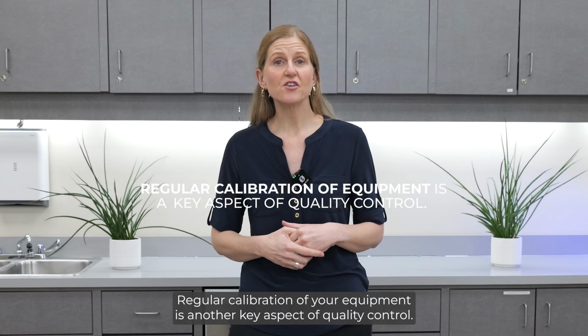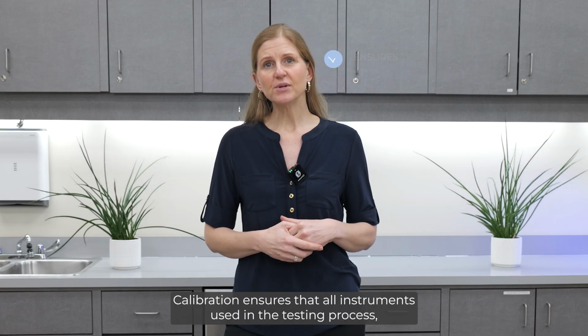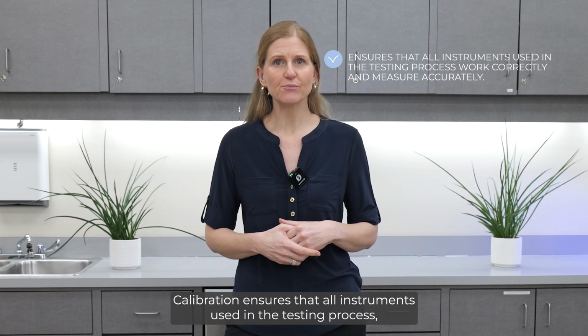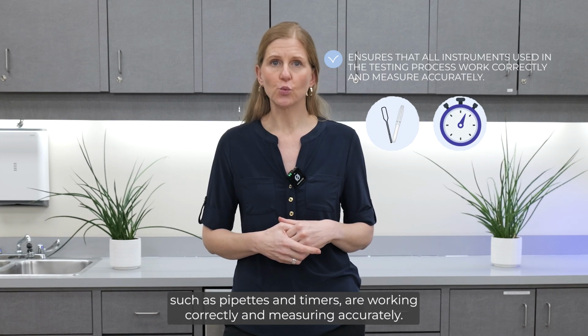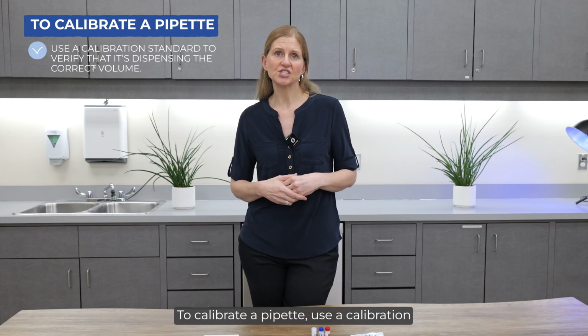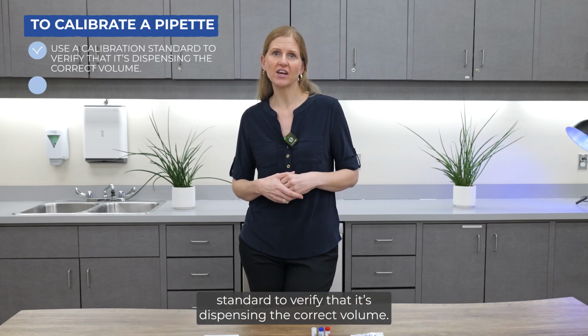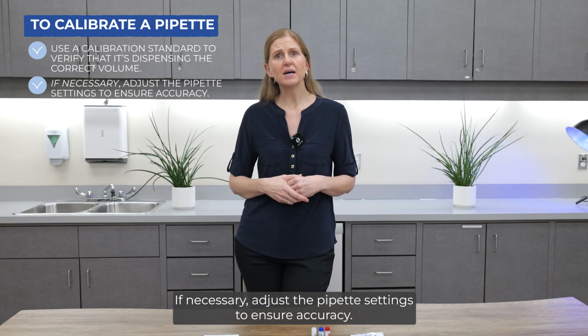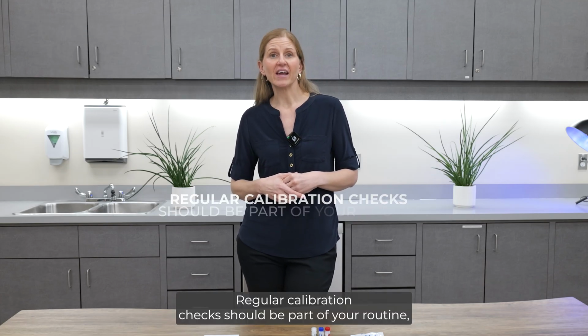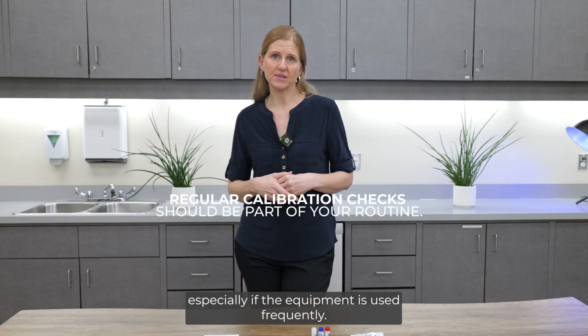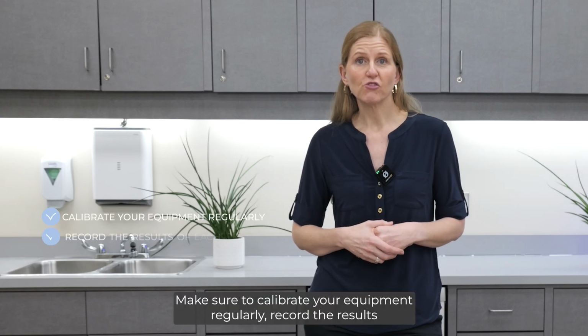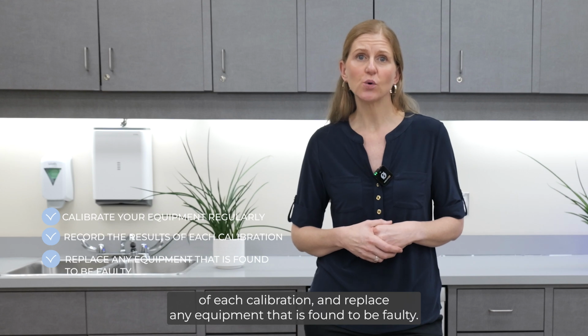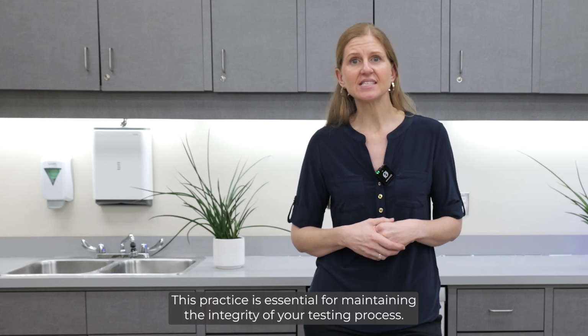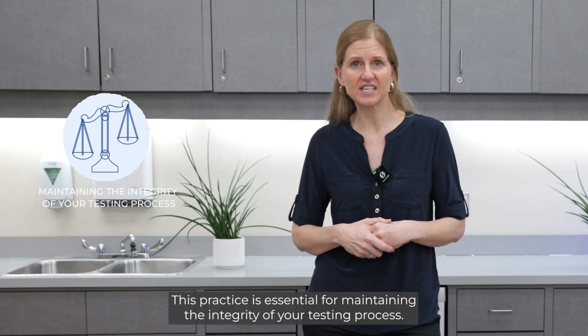Calibration of your equipment is another key aspect of quality control. Calibration ensures that all instruments used in the testing process, such as pipettes and timers, are working correctly and measuring accurately. To calibrate a pipette, use a calibration standard to verify that it's dispensing the correct volume. If necessary, adjust the pipette settings to ensure accuracy. Regular calibration checks should be part of your routine, especially if the equipment is used frequently. Make sure to calibrate your equipment regularly. Record the results of each calibration and replace any equipment that is found to be faulty. This practice is essential for maintaining the integrity of your testing process.